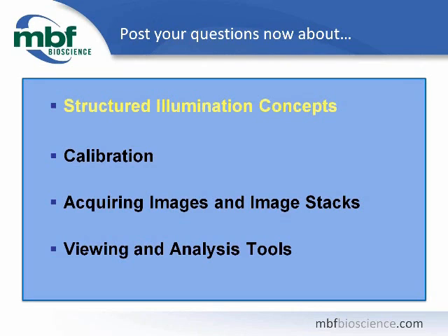Let's pause and answer questions about structured illumination concepts. Someone has asked if we must use a monochrome camera — the answer is yes, and you also need a high bit depth camera for the extra dynamic range. Someone asked if there is minor vibration during image capture and whether imaging would be affected seriously. Ideally you'll have a very stable system. If the grid moves imprecisely, your final image quality would be affected dramatically and you would have strong residual grid lines.